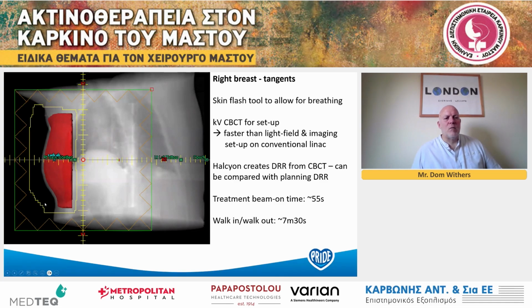So we have added skin flash here manually on the fields in order to cope with any breathing. This is a very traditional thing that's been done for 3D conformal planning for many decades. The Halcyon from the cone beam can create these DRRs, so you can actually see how much lung and where the contour is. And of course, there's also the 3D image matching that you're doing with the cone beam itself. The treatment beam on time, I've said there, is 55 seconds. That's the total amount of time of treatment. So that's from the beginning of the first beam to the end of the second beam.